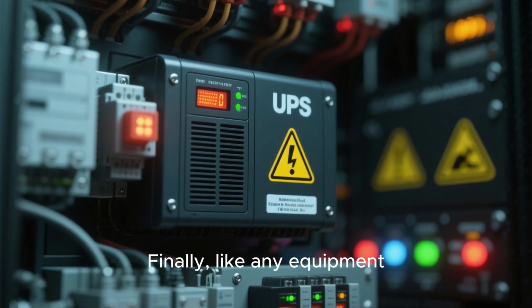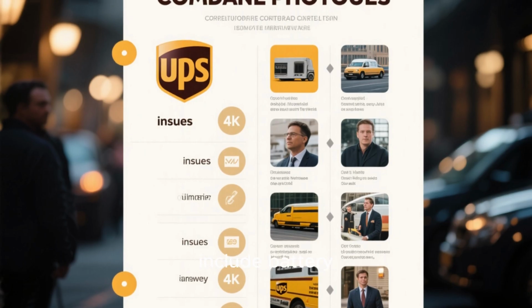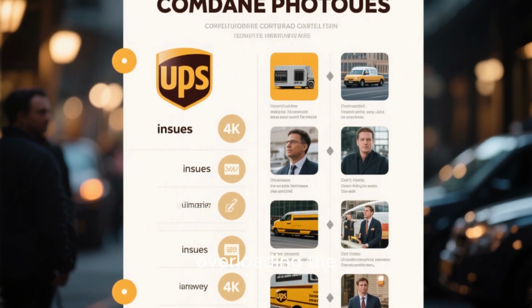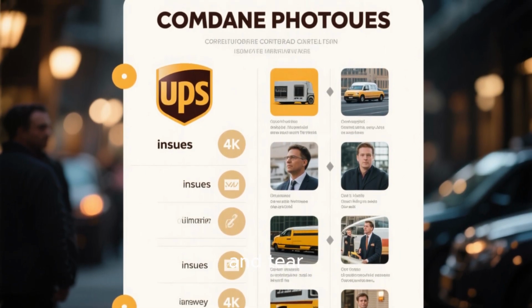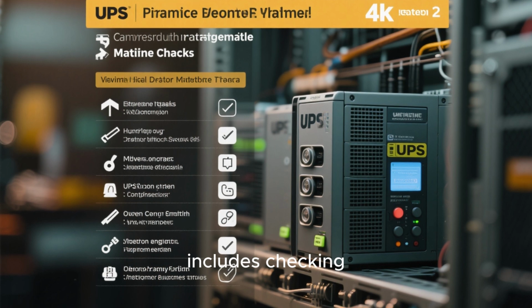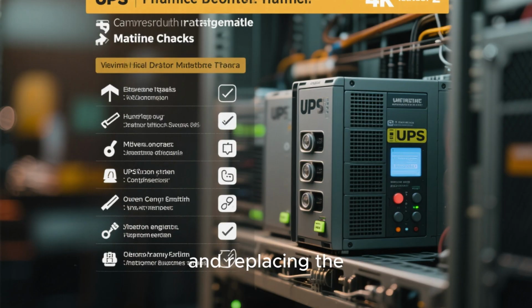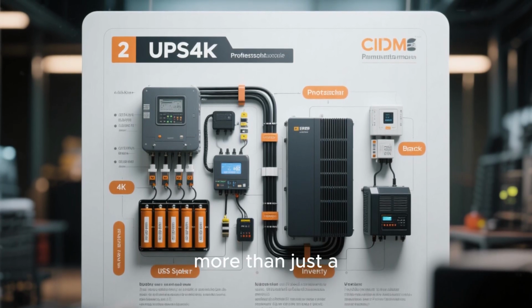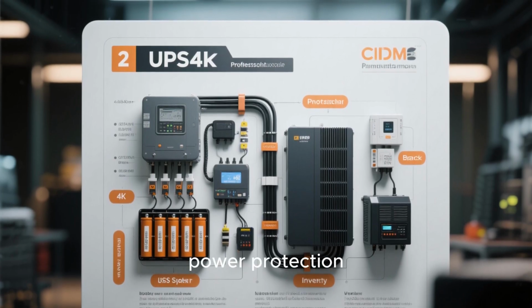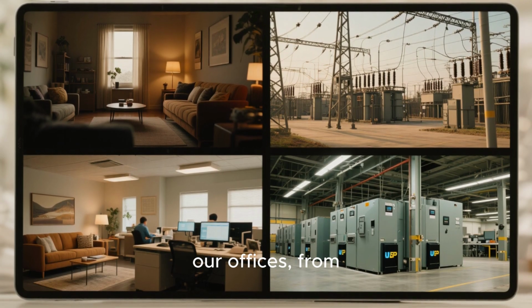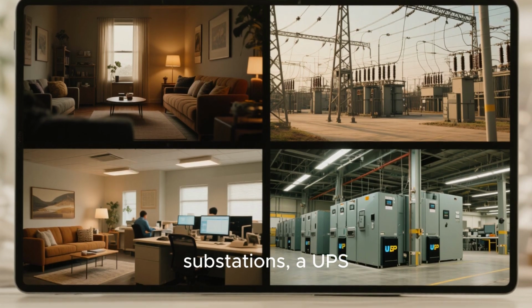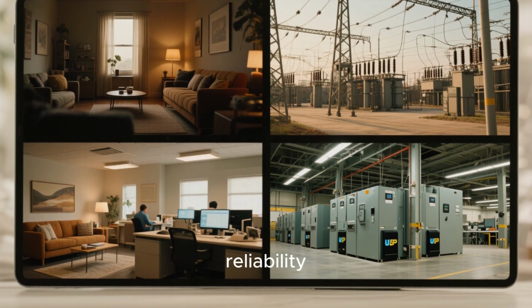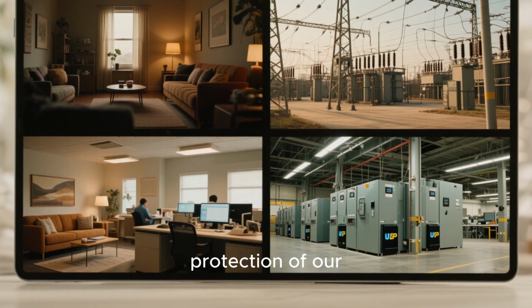Finally, like any equipment, a UPS can fail. Common issues include battery failure, overloading the system, overheating due to poor ventilation, and just general wear and tear. Regular maintenance is key. This includes checking the batteries, performing load tests, keeping the ventilation clean, and replacing the batteries on schedule. So, to wrap it all up, a UPS is much more than just a backup battery. It's a complete power protection system. From our homes to our offices, from factories to critical power substations, a UPS ensures safety, reliability, continuity, and the protection of our valuable equipment.